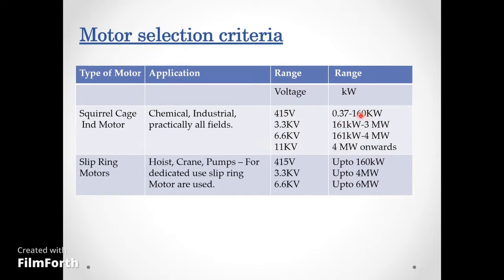Depending on the voltage level available, you can select your motor rating. For example, a 160kW motor can be started at 415V. There is no strict thumb rule — even a 180kW or 100kW motor can be started on 415V. These are just guidelines to select voltage levels as per availability.